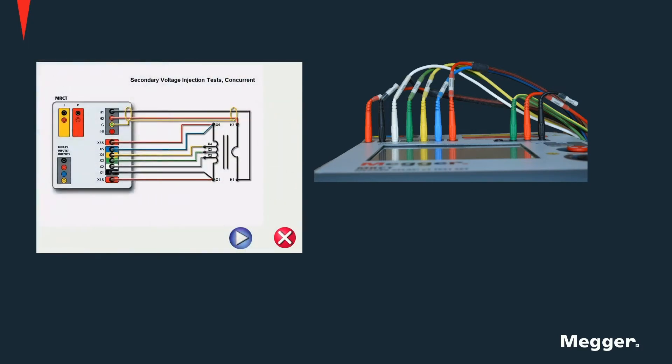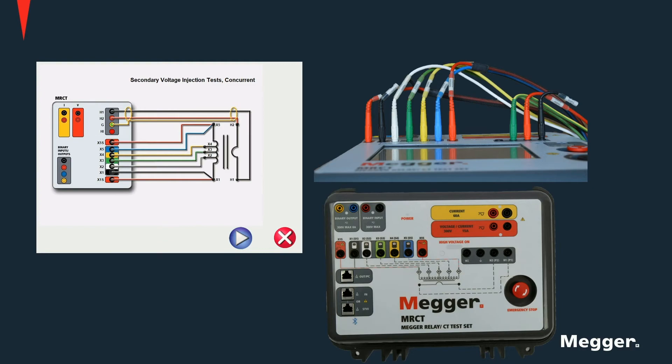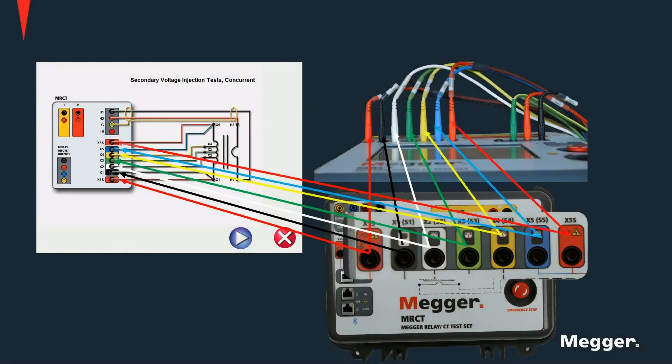When it comes to testing with the MRCT, it is important to remember that most tests can be performed with a single connection diagram. For example, for the five-tap CT depicted here, we can perform at the same time or without changing connections tests like winding resistance, ratio, insulation resistance, and saturation curve, and we can even perform a demagnetization procedure without ever having to change the connections on the MRCT. You should remember to always connect X1S together with X1S1 and X5S with X5S5. These leads should always be connected to the main tabs of the CT under test.